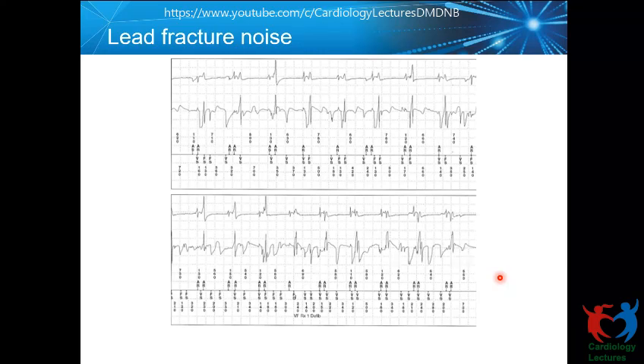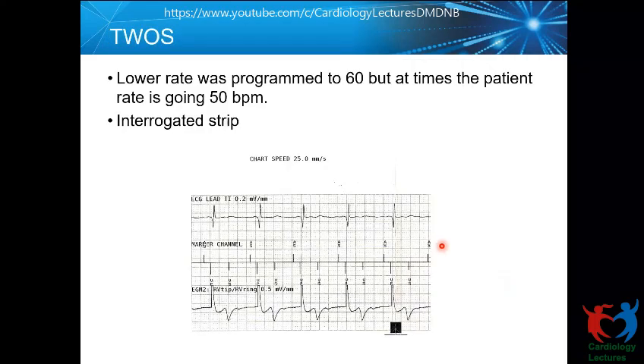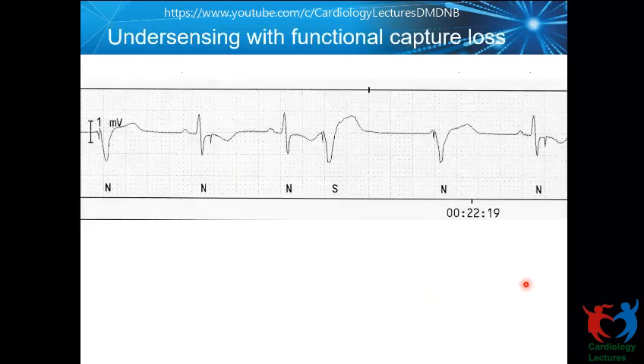And this is an example of T wave oversensing that you can see here. This is the ventricular sense happening, and this is another ventricular sensing on the T wave. You will not see that in a conventional pacemaker. Even if it happens, it will fall in the refractory period. We will see that in good detail in the timing cycle that we're going to take up.